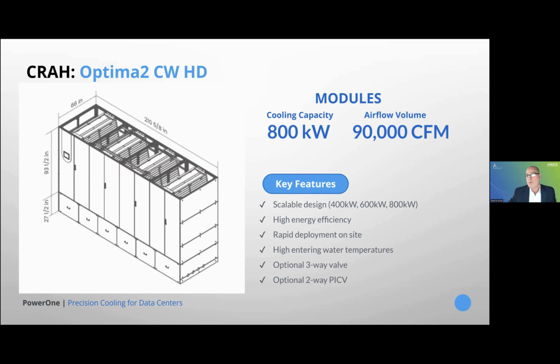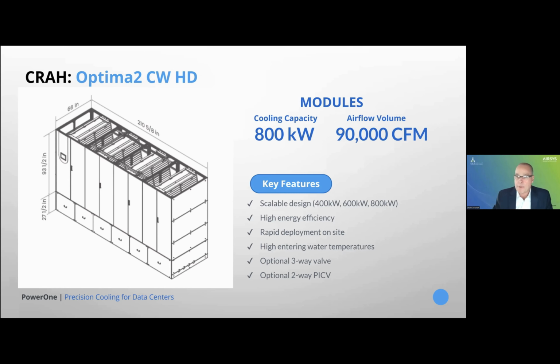This is our Optima2 chilled water high density. This is a one frame solution as opposed to the smaller 60 kW modulars. We have different capacities of 400, 600, and 800 kW, where we're getting up to over 90,000 CFM or 1 megawatt of cooling. Again, this is a product that ships in 2 pieces, the coil section and the fan section. You have the ability to run higher entering water temperatures. This gives us the ability to, again, rapidly deploy, which is the theme for every data center. But again, it comes in the ability for us to address your particular needs depending on what your cooling requirements are.